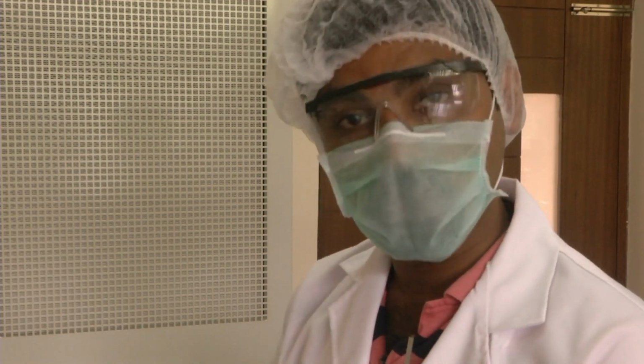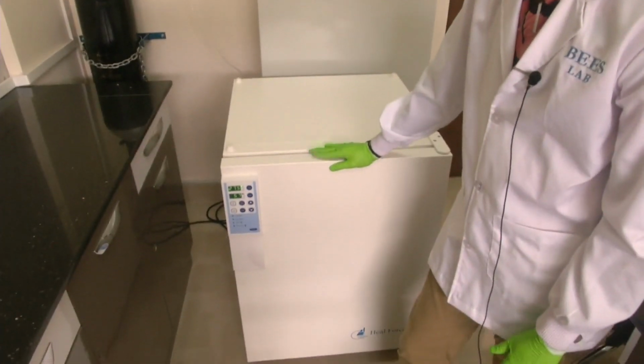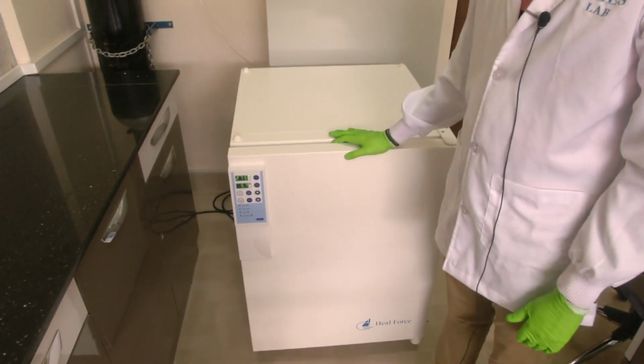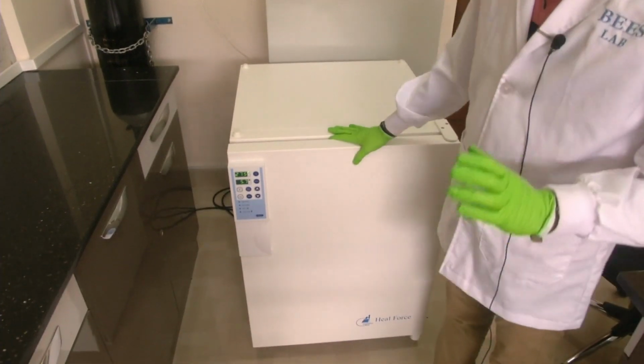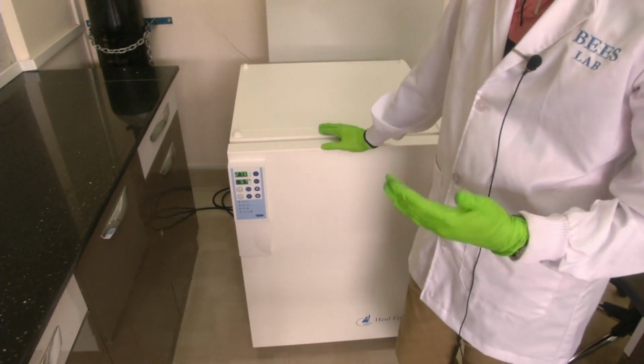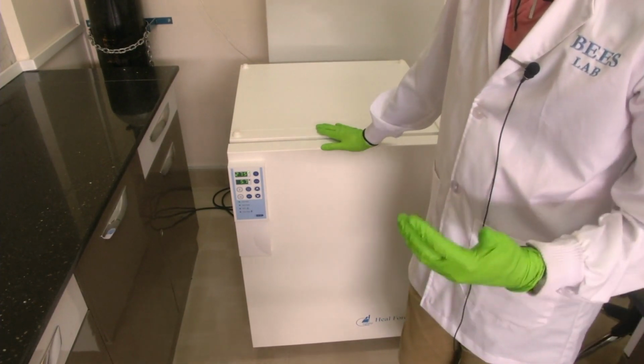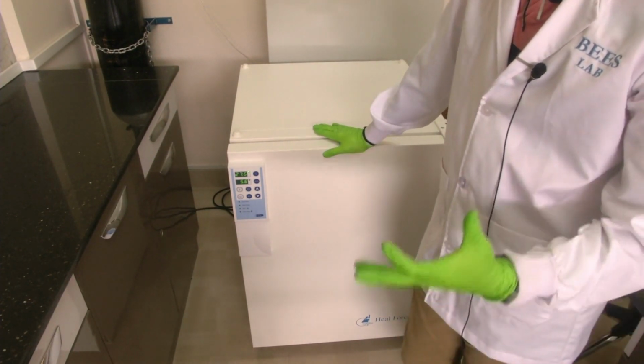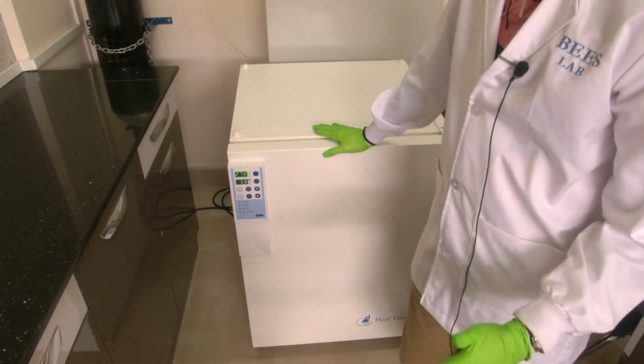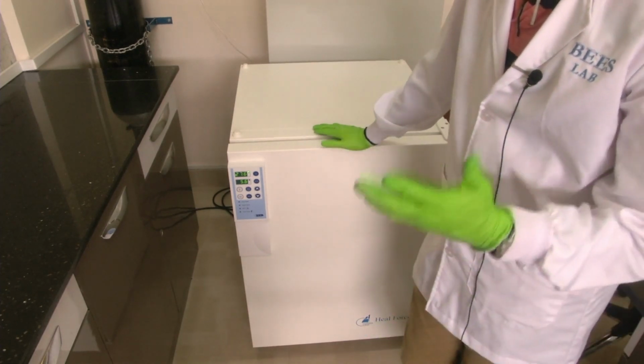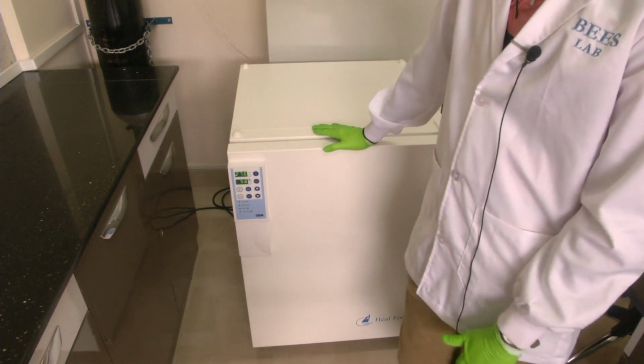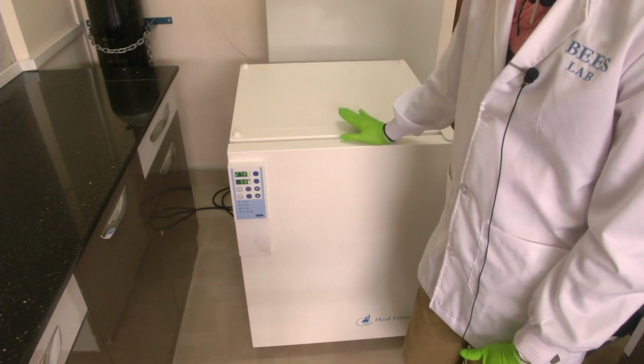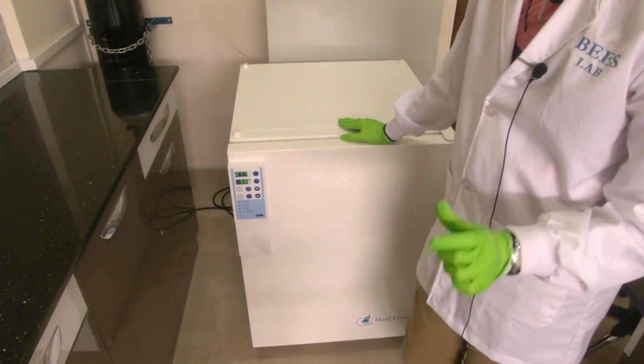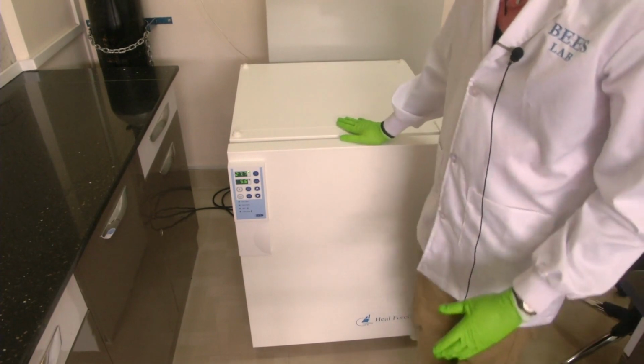Today we are going to see what is called an incubator, or usually a CO2 incubator. So this is the CO2 incubator, you can see. For cells to grow in an incubated environment, the major parameters required are that you should provide 37 degrees Celsius ambient temperature, 5% carbon dioxide level and 95% relative humidity. This equipment will make sure that these parameters are provided to the cells and they can grow without any contamination. So, first let us see the control panel.